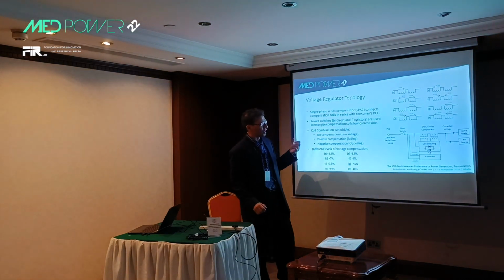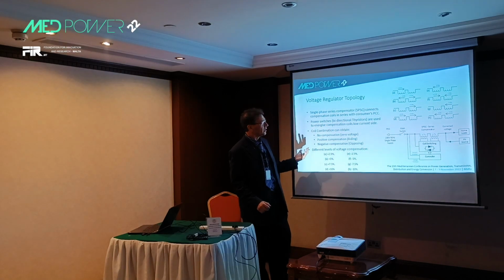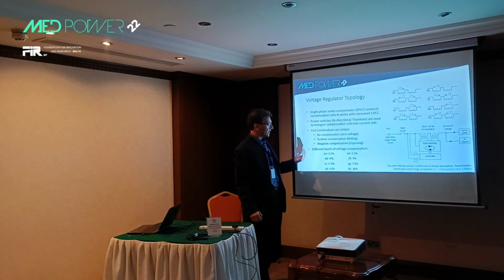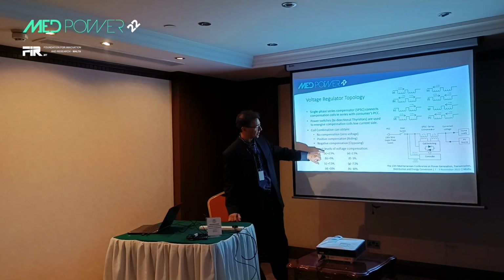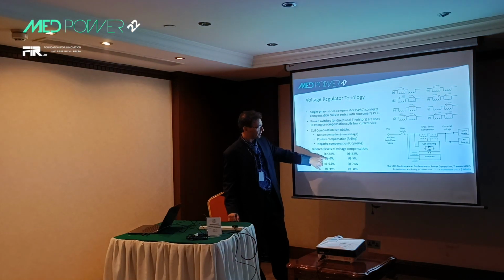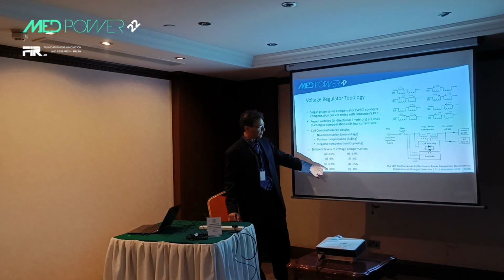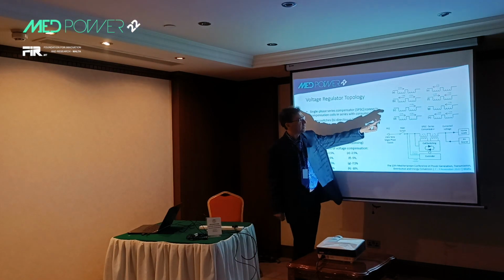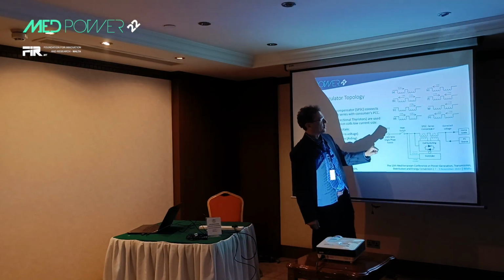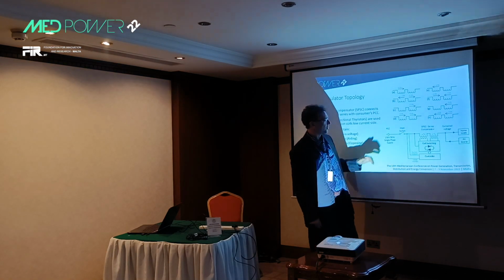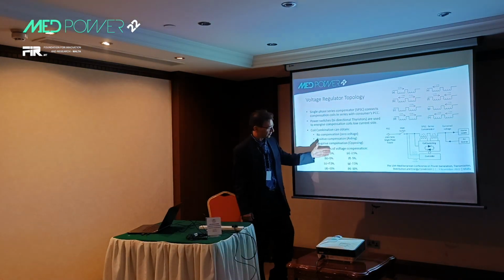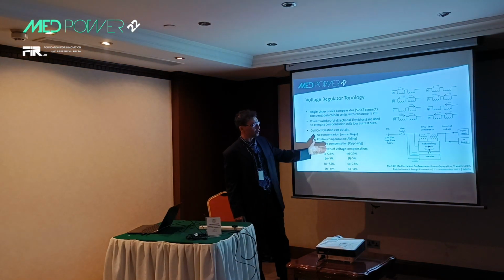And how is the principle of operation going to be? So when we want to increase our voltage, we can increase it at levels of plus 2.5, plus 5, plus 7.5, and plus 10. How is that done? It's done by switching the coils in series. Okay, so we can switch them in series to achieve whatever additional voltage we want to add in this direction.